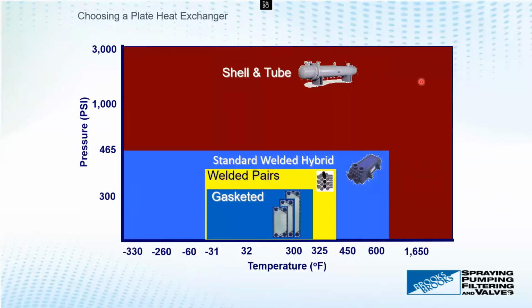And then we talked about at great length when you can use a plate and frame versus a shell and tube. We talked about shell and tubes being essentially welded vessels with piping type gaskets as the only seals. So if your piping system can take what's going on inside of your system, a shell and tube should be able to take it. However, they're the least efficient or mid-efficient in exchanging heat. So therefore they take about 5 to 1. So 5 times the material, 5 times the space, and they have 1/5 of the efficiency, give or take. It's kind of a rule of thumb. And when you start talking about gasketed plate and frame heat exchangers, they are limited for their temperatures and pressures, but they're tremendously efficient relative to a shell and tube.